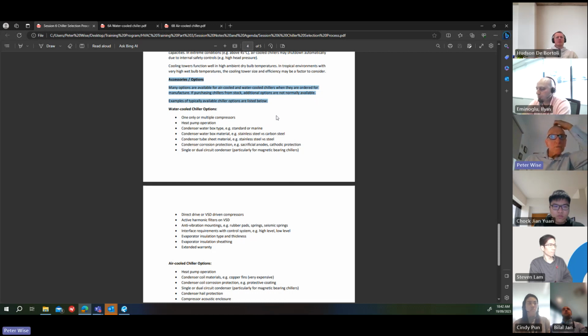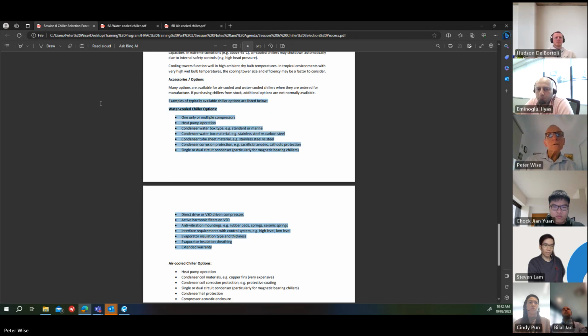when you order a chiller, you can ask for numerous options. If you're purchasing a chiller from stock, you won't get the options normally that you might want. But when you order one, you can order any options you like as long as they're available. And here's some examples of typical options. So for water-cooled chillers, you can have one compressor or multiple compressors. So as I said, with a screw or scroll or magnetic bearing compressors, you can have multiple compressors if you need to increase the capacity. You can get heat pump operation, condenser water boxes, standard or marine type. So I'll just look at that a bit closer.